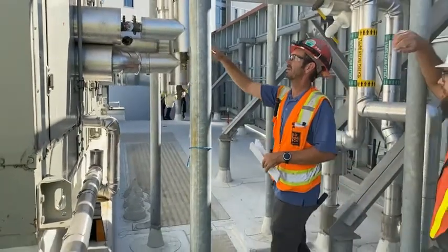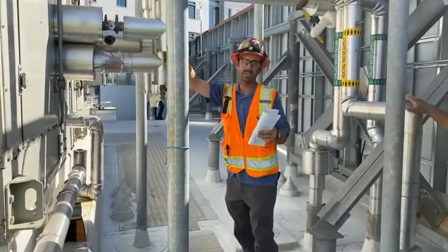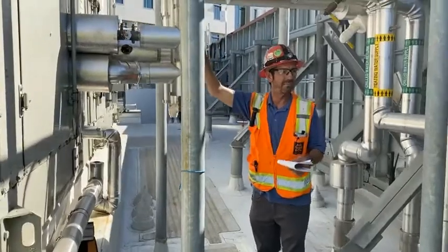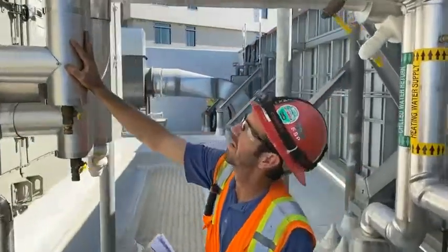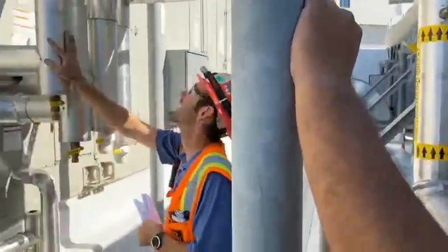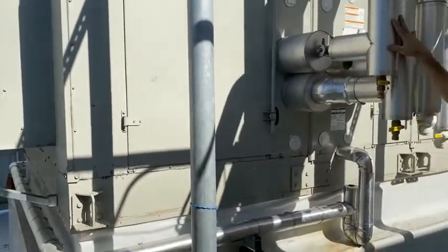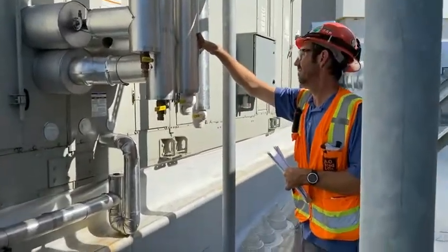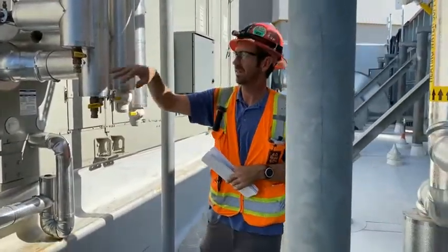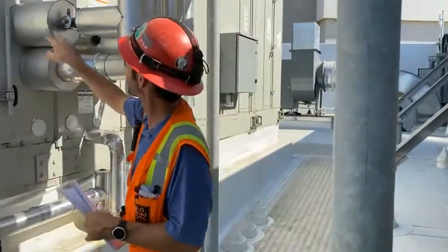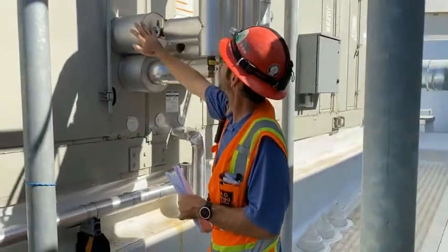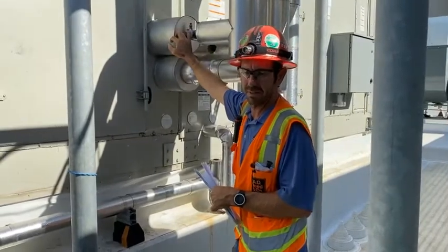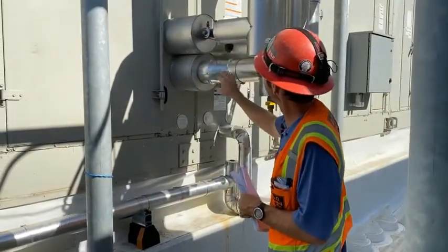Then we have, over there we didn't talk about the piping, but we mentioned it in an earlier video on the piping. We have hot water and chilled water. We got hot water here and then chilled water here. Remember, we have balance valves to keep the flow going through the units equally. We shouldn't need to turn these off. There's no shutoff valve on the supply right here.